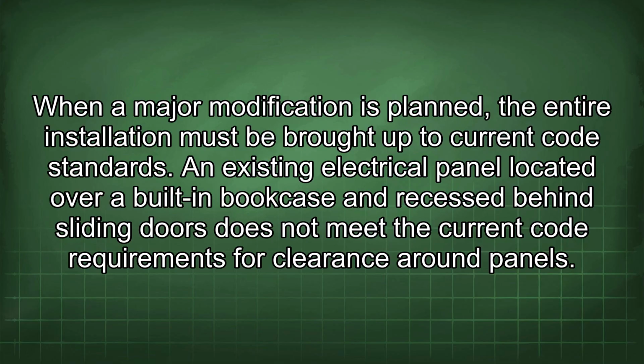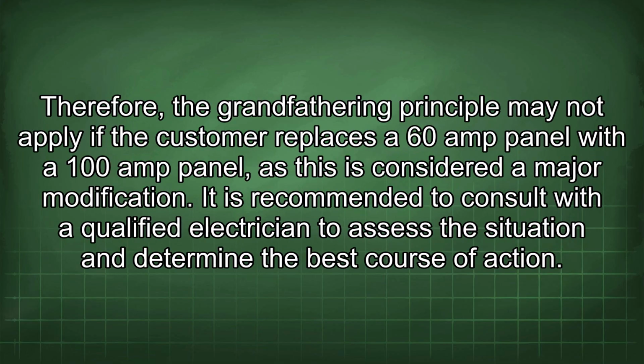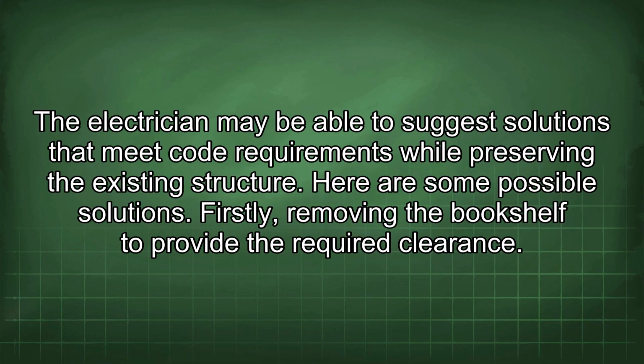An existing electrical panel located over a built-in bookcase and recessed behind sliding doors does not meet the current code requirements for clearance around panels. Therefore, the grandfathering principle may not apply if the customer replaces a 60-amp panel with a 100-amp panel, as this is considered a major modification. It is recommended to consult with a qualified electrician to assess the situation and determine the best course of action. The electrician may be able to suggest solutions that meet code requirements while preserving the existing structure.